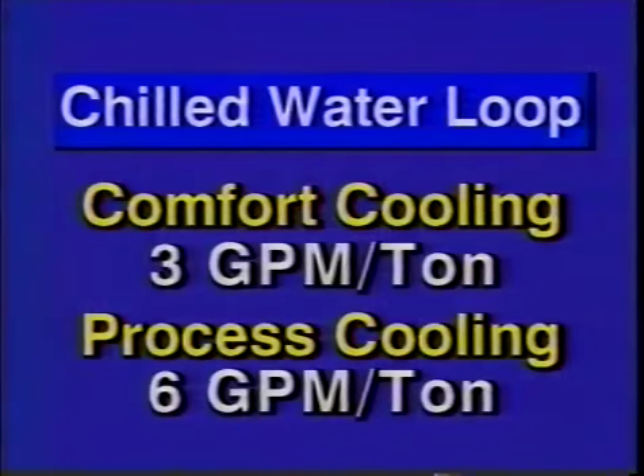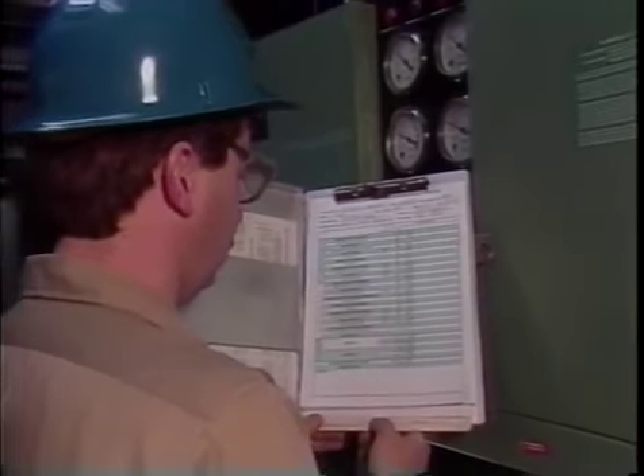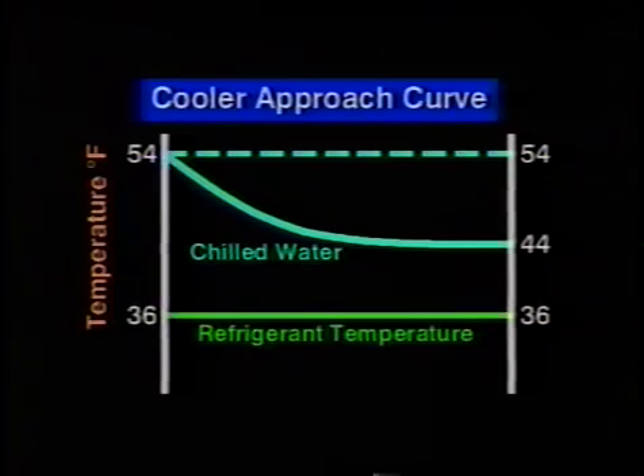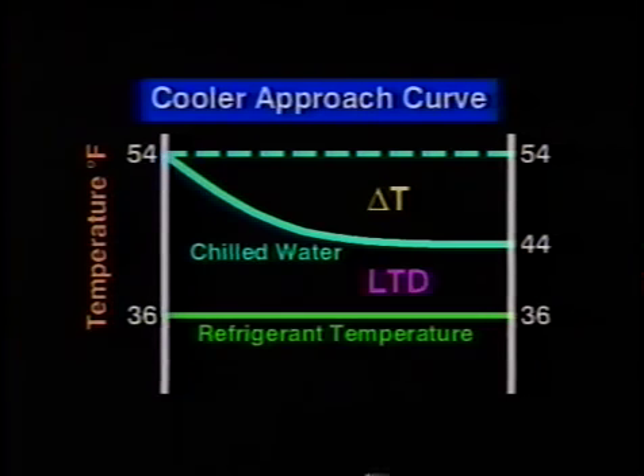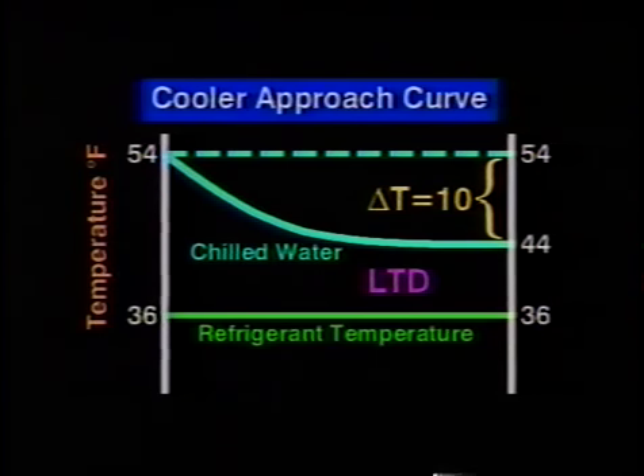For proper control, the chilled water loop must contain at least 3 gallons per ton of unit capacity for comfort cooling and 6 gallons per ton for process cooling. The most important tool in troubleshooting is the maintenance log, which provides an ongoing record of system temperatures and pressures and maintenance work. When troubleshooting, approach curves are useful for showing the relationship between the circulating water and the saturated refrigerant temperatures. Two important relationships shown on approach curves are delta T and LTD. Delta T is the temperature drop or rise of the water as it goes through the cooler or condenser and is usually about 10 degrees Fahrenheit.